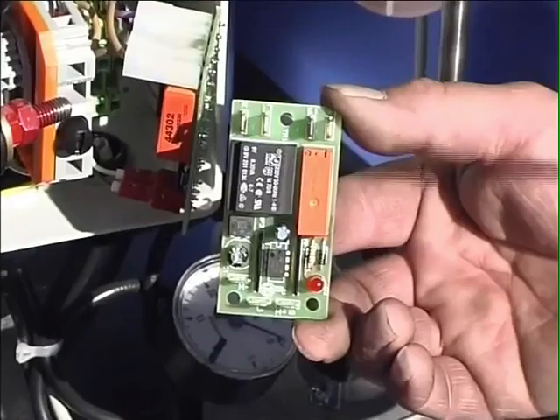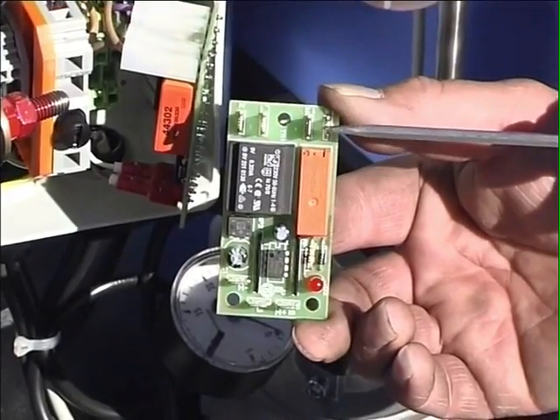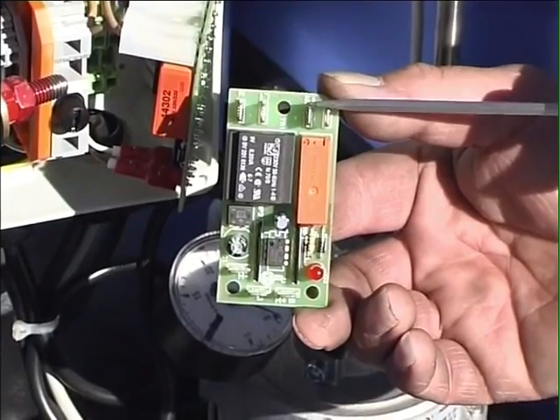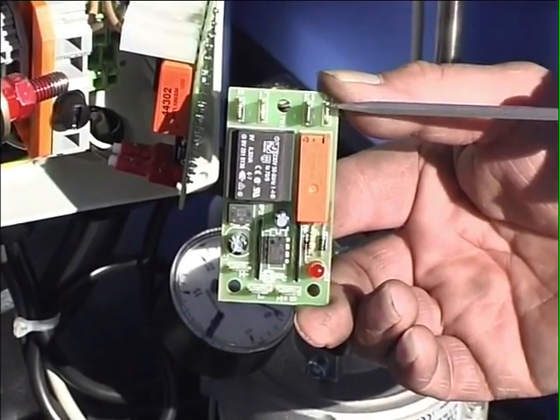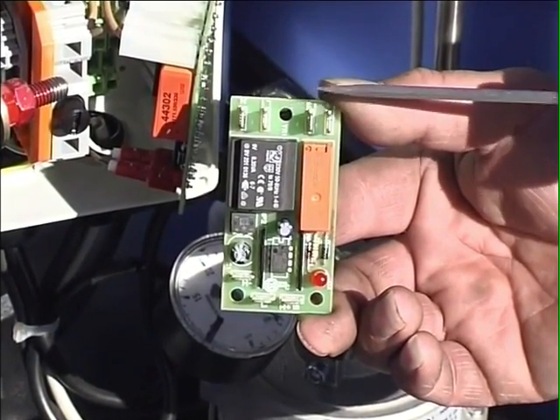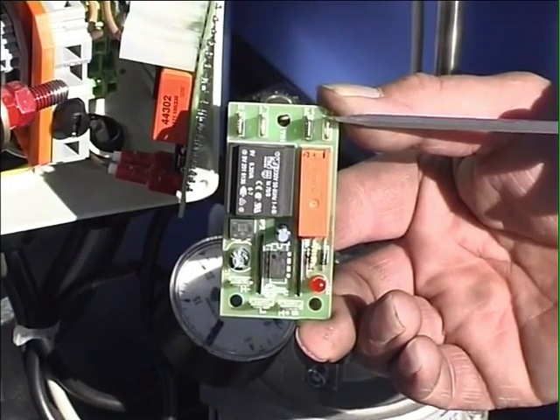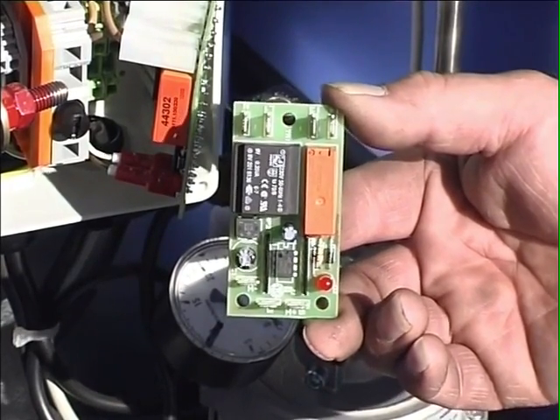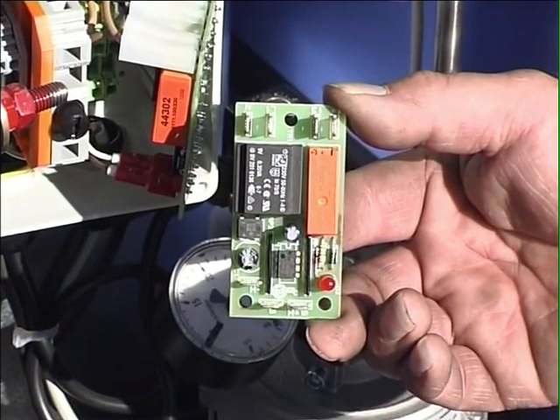By withdrawing and plugging a contact, you can check the function of the float switch. If the machine operates now, the circuit board is defective. To check the magnetic valve, pull the plug and bridge the 2 cables of the magnetic valve. You must have first checked to see whether there is 230 volts.